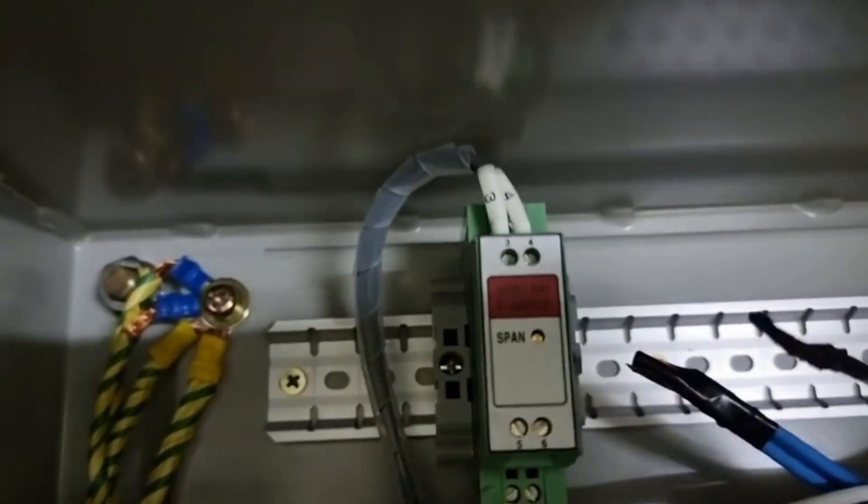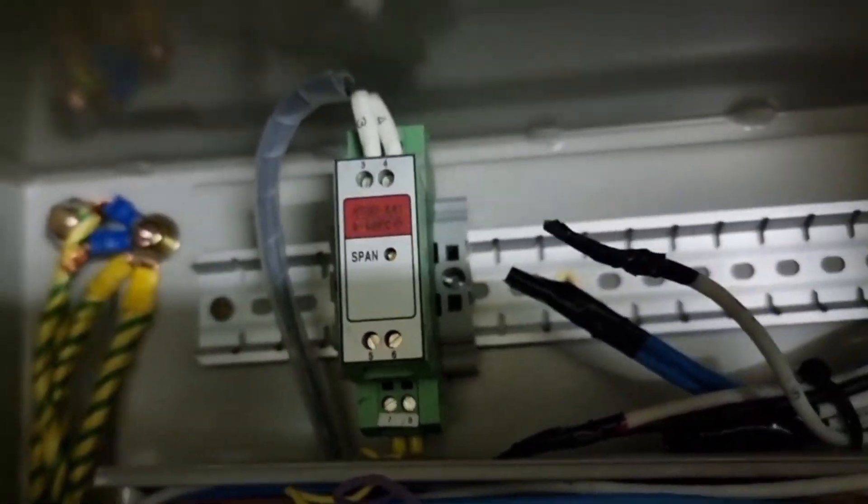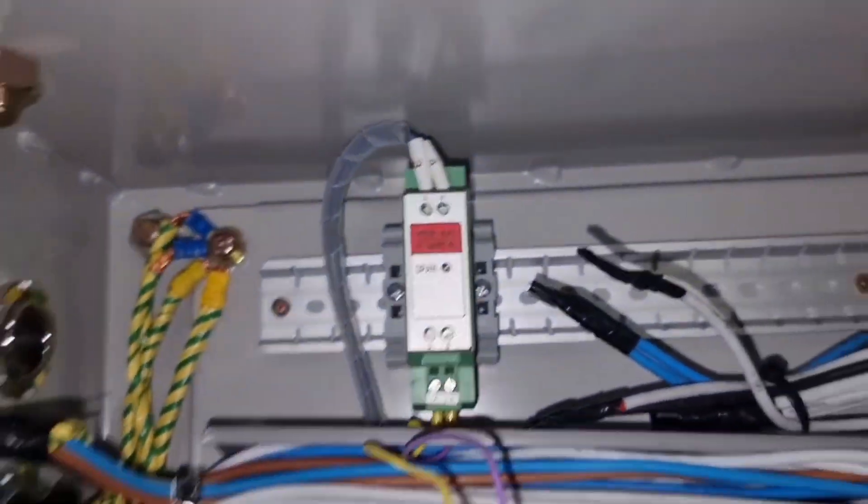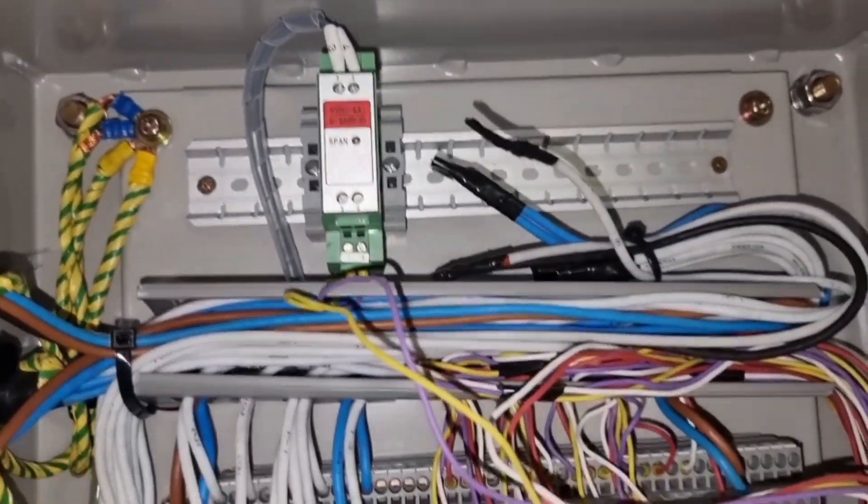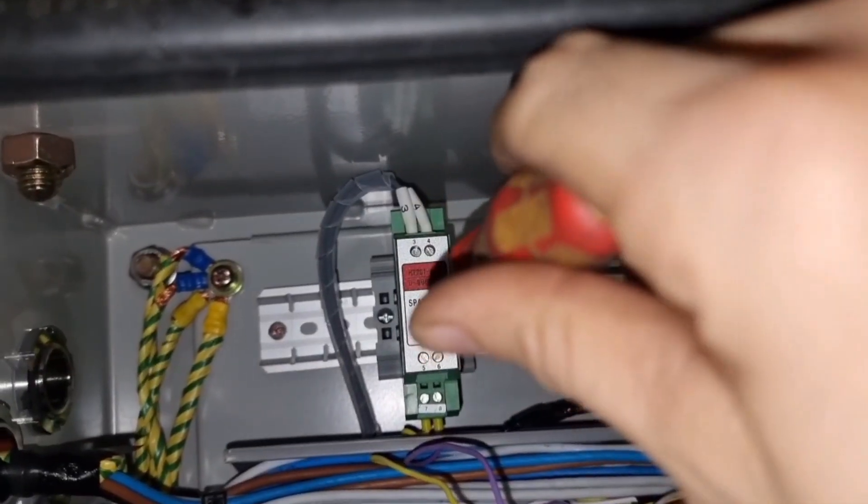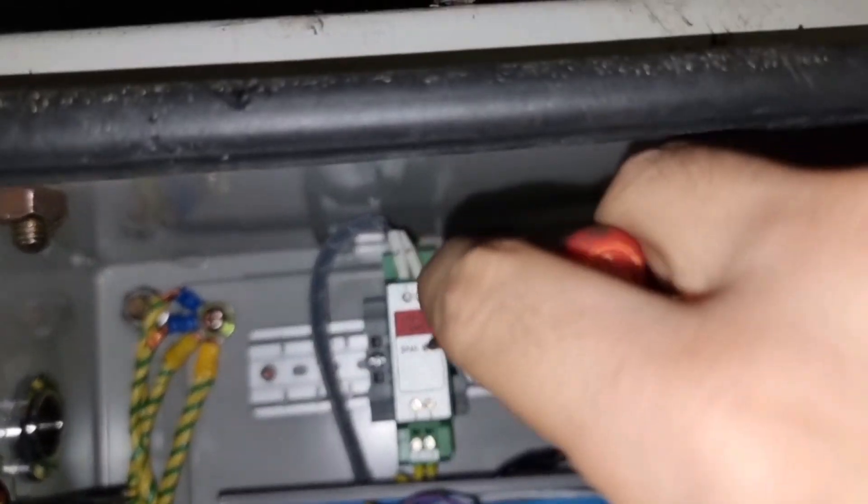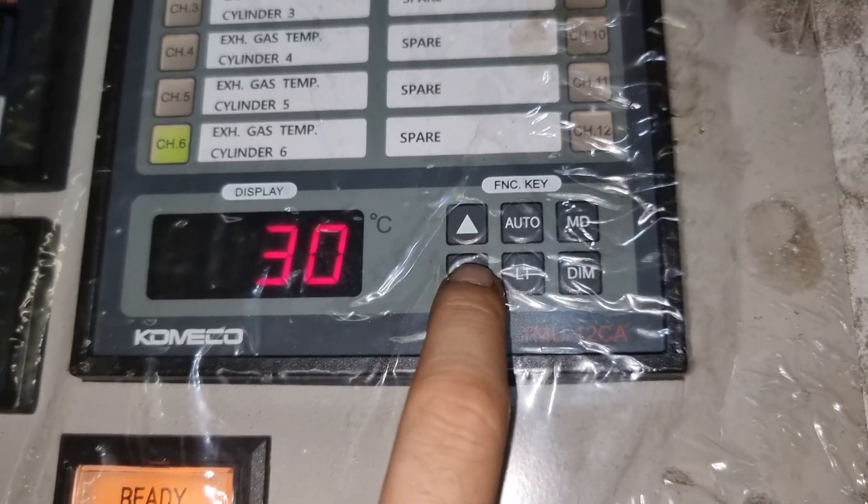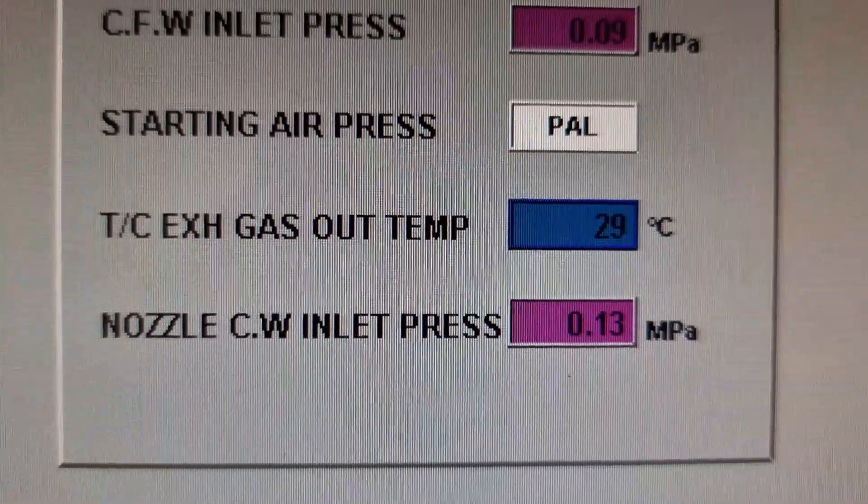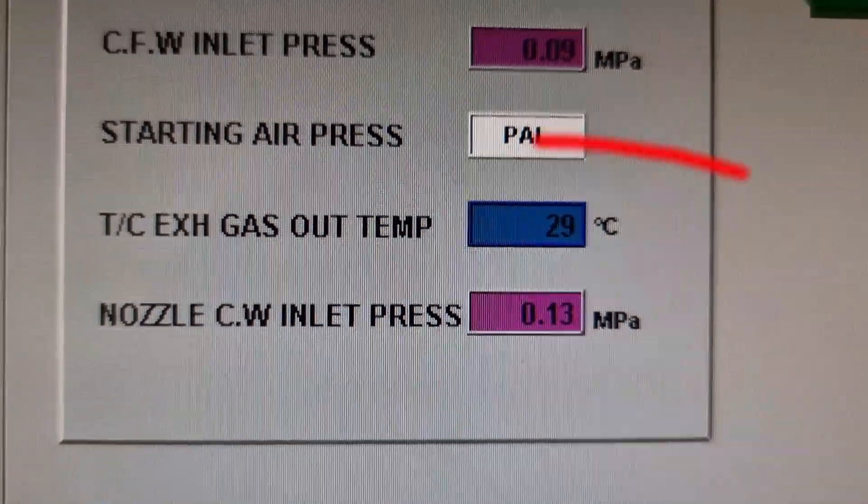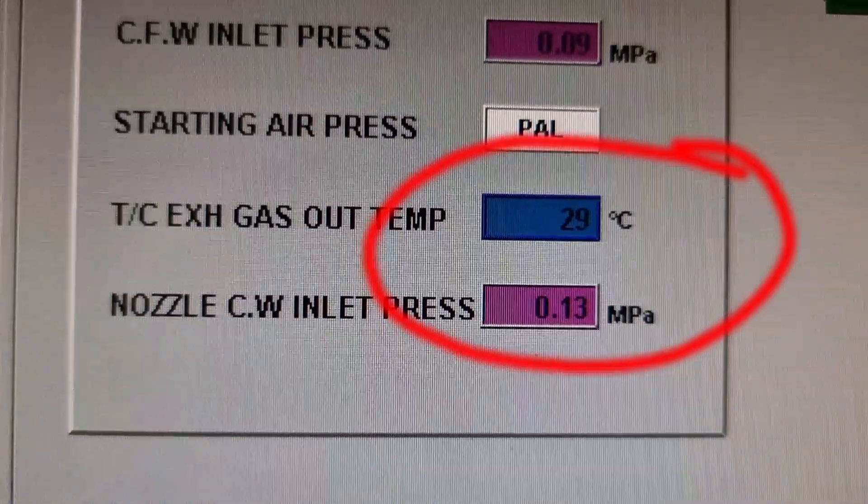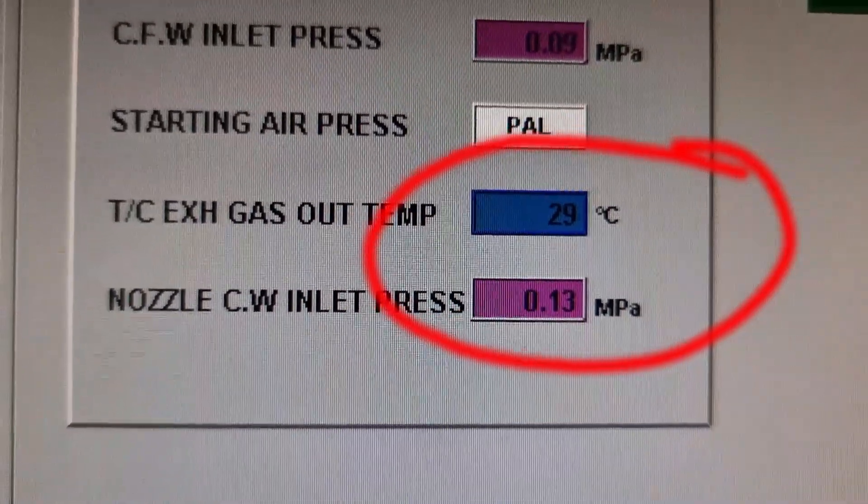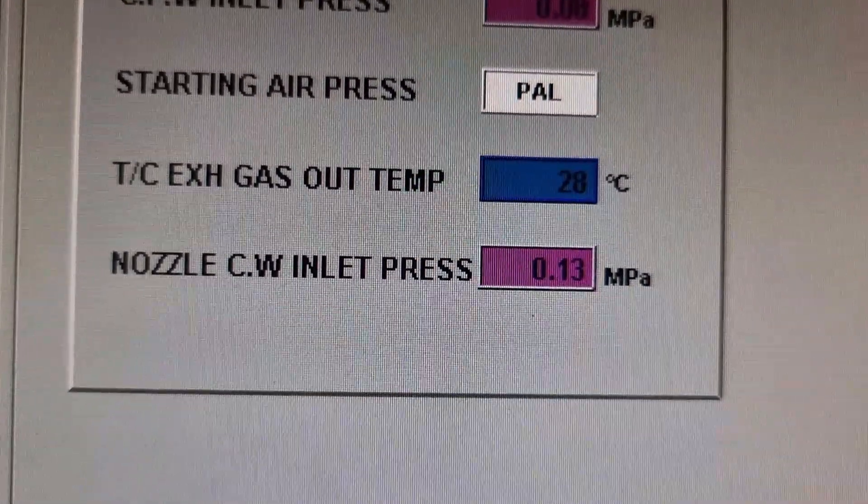I just need to turn counterclockwise the span of the amplifier until I will match the one that is in the control panel display. So after thorough checking, we have fixed the mixed wiring on the turbocharger outlet temperature and we also calibrated it.